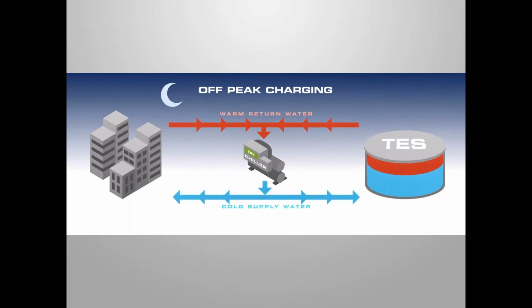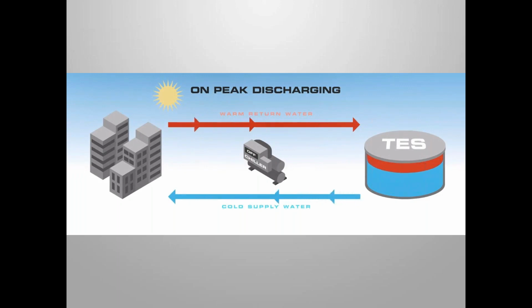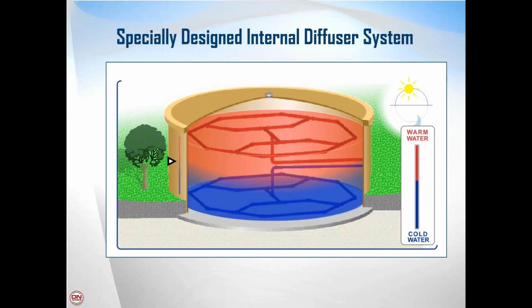And that charging and discharging, that's a typical operation that happens every day, where at night or during off-peak hours, the tank is charged up, and then during the daytime or peak hours, that cold water provides the cooling for the campus. And inside the tank, the cold and warm return water is stratified in there. You're looking through the side wall of one of our tanks, and inside the tank, we have specially designed a network of piping or a plate type diffuser system that takes the cold or warm water that's entering or leaving the tank and slows it down over the cross-sectional area of the tank.